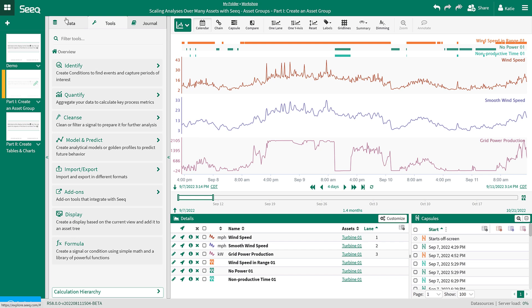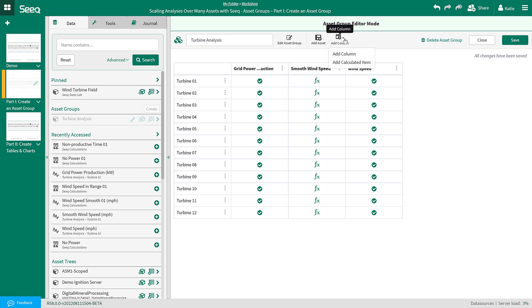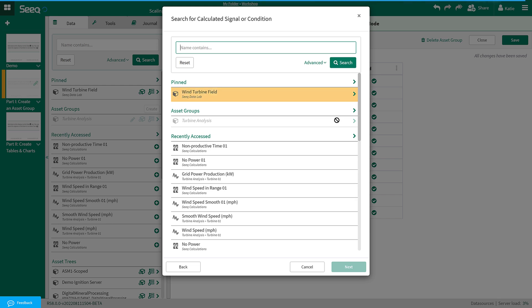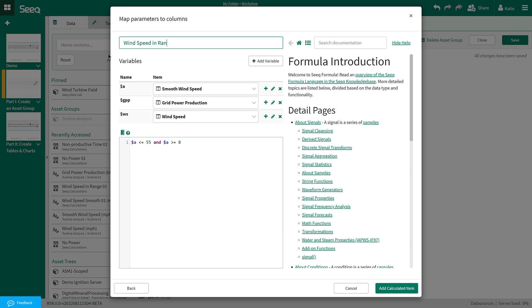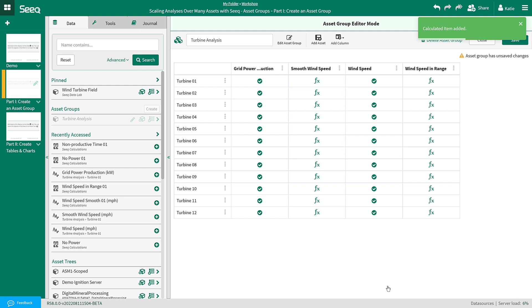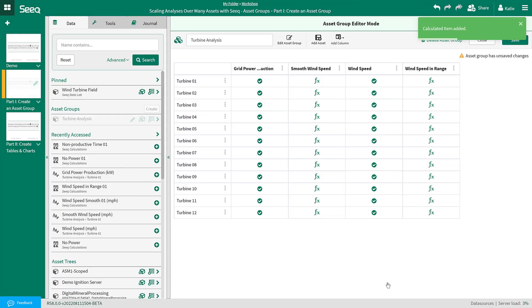Now I will build each of these conditions into the asset group. This is done very similarly to the smooth wind speed signal we added. I will navigate to add column, add calculated item, existing Seeq item, and select wind speed in range. You will notice that again the formula items default to the items in the asset group, showing the table icon. It looks good, so I will add it to the tree. Now it has populated the same formula for all the turbines. I know that turbine 9 has a different wind speed range, so I am going to edit that formula by clicking on it and updating the parameters. If needed, I could also apply these changes to the entire column by using the checkbox in the lower right.